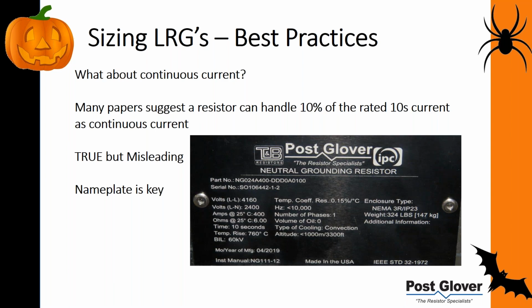I would say that the nameplate is key. If you were looking for a specific amount of continuous current and you just assume, or you ask the manufacturer, oh, can this handle this amount of current? First of all, you may not be taking into consideration the series of events I just laid out for you, but also you may not get what you want. I wouldn't necessarily trust the manufacturer for the information. That's not a good thing to say, but if it's not on the nameplate, why isn't it on the nameplate? If this can handle 100 amps continuous current, then why wouldn't you put it on the nameplate?